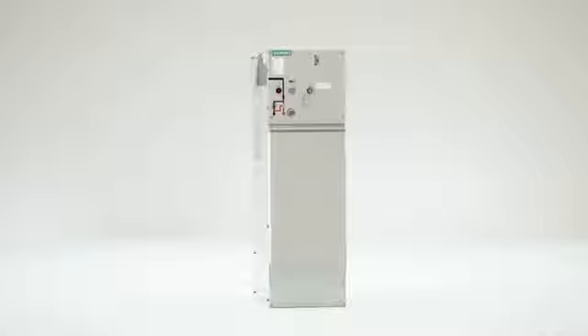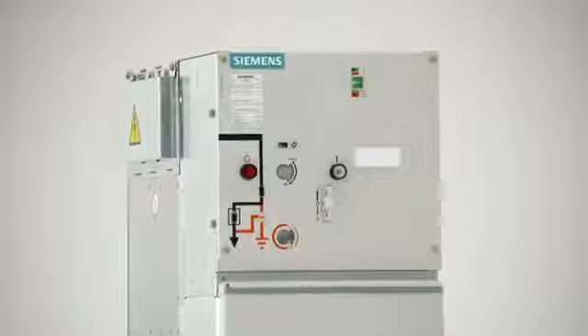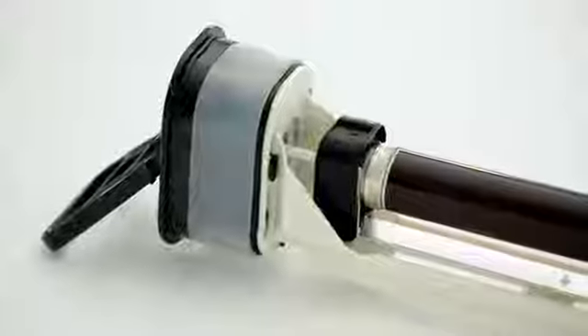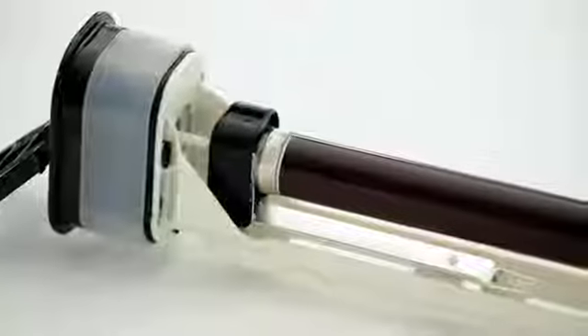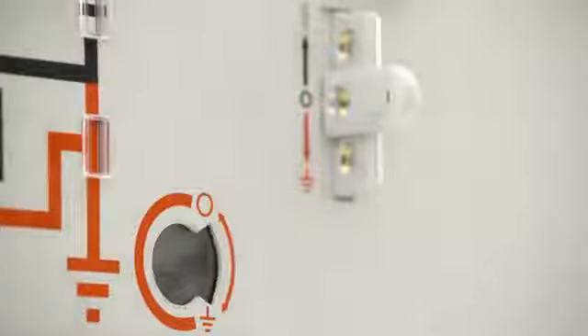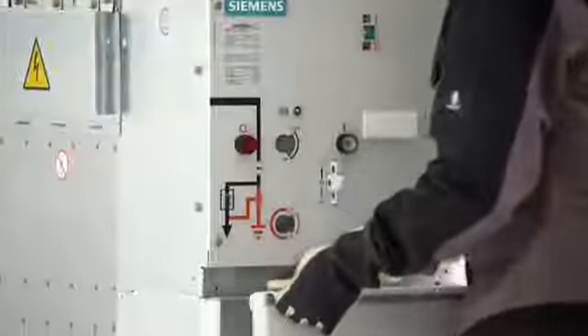Besides its distribution function, the 8DJH transformer feeder also has the task of protecting the downstream transformer. Here, short-circuit protection is taken over by high-voltage, high-rupturing capacity fuses. After the feeder has been de-energized and earthed, the cable compartment cover can be opened. The fuse can then be easily and quickly replaced without using tools. The fuses are mounted in single-pole enclosed boxes made of cast resin.